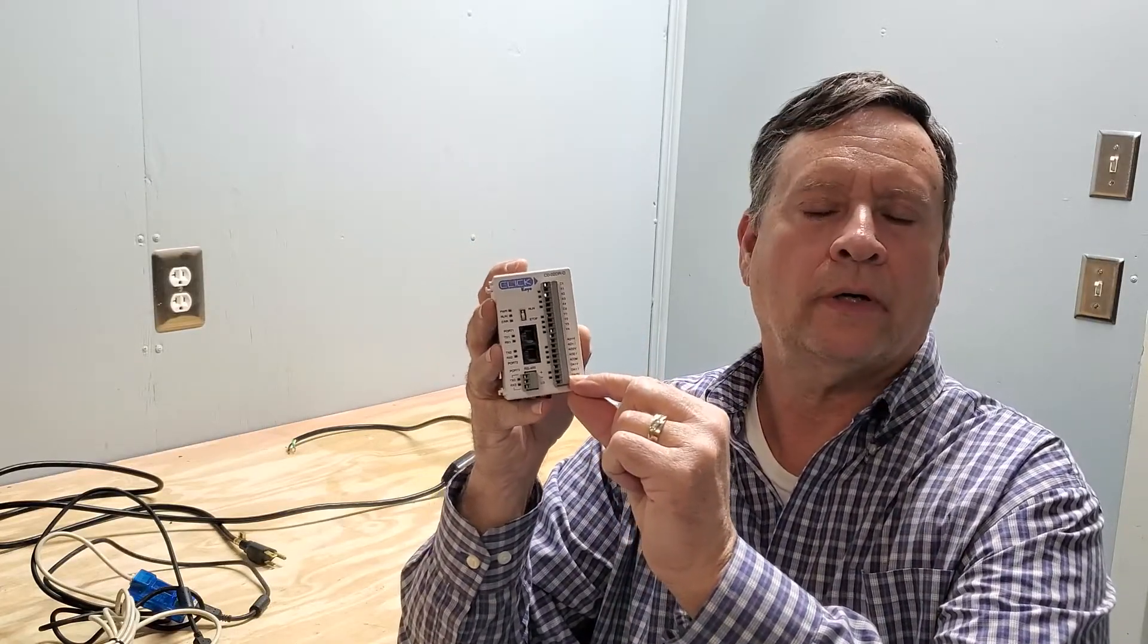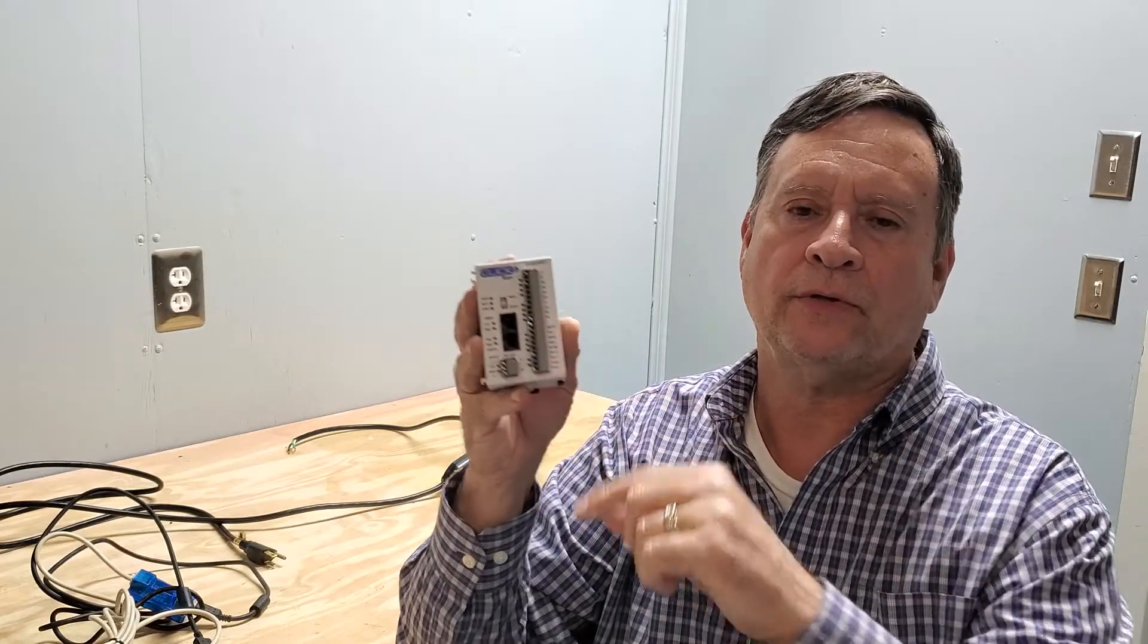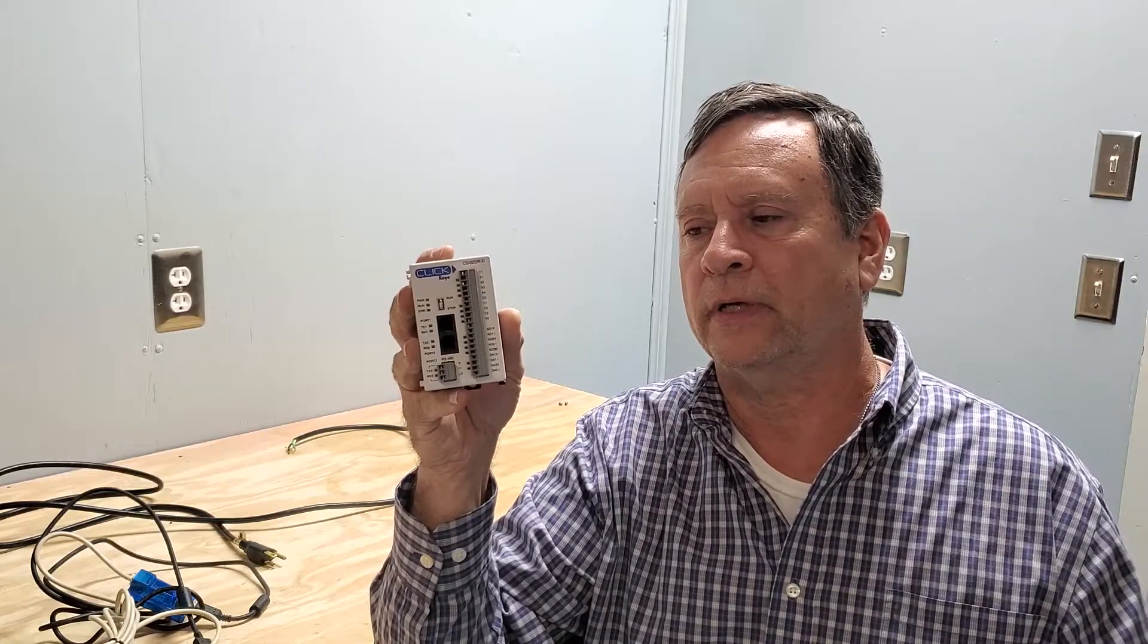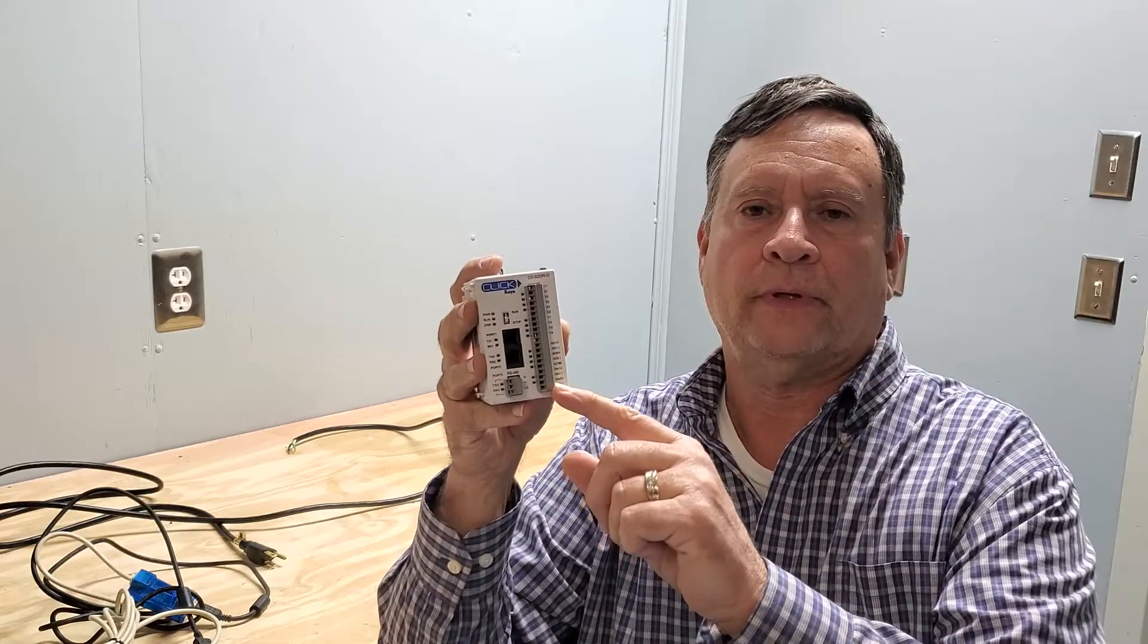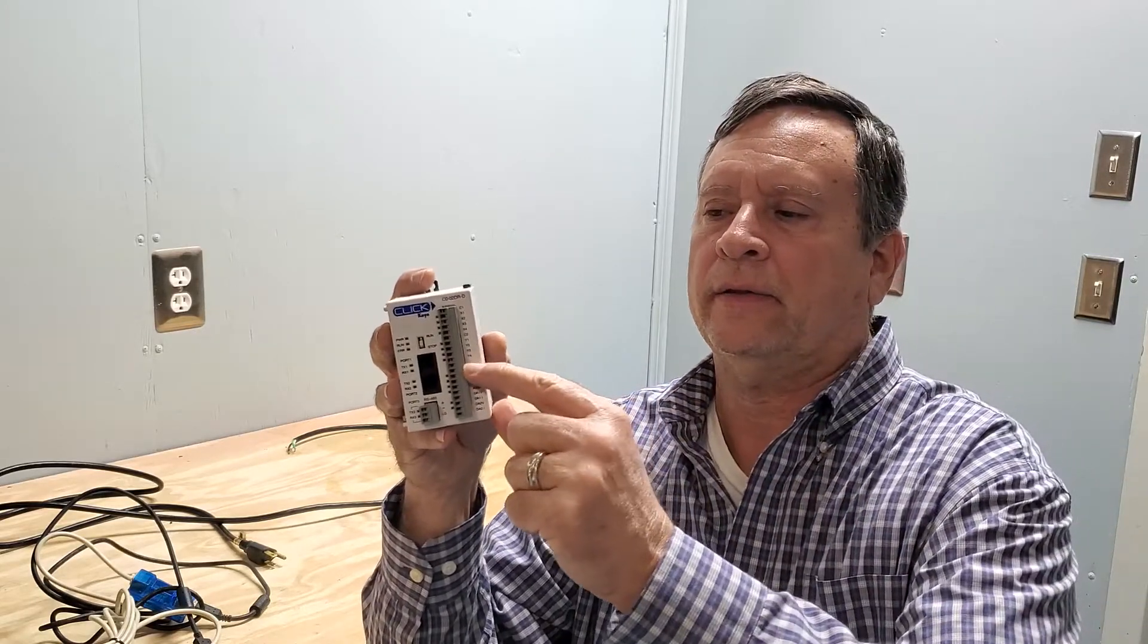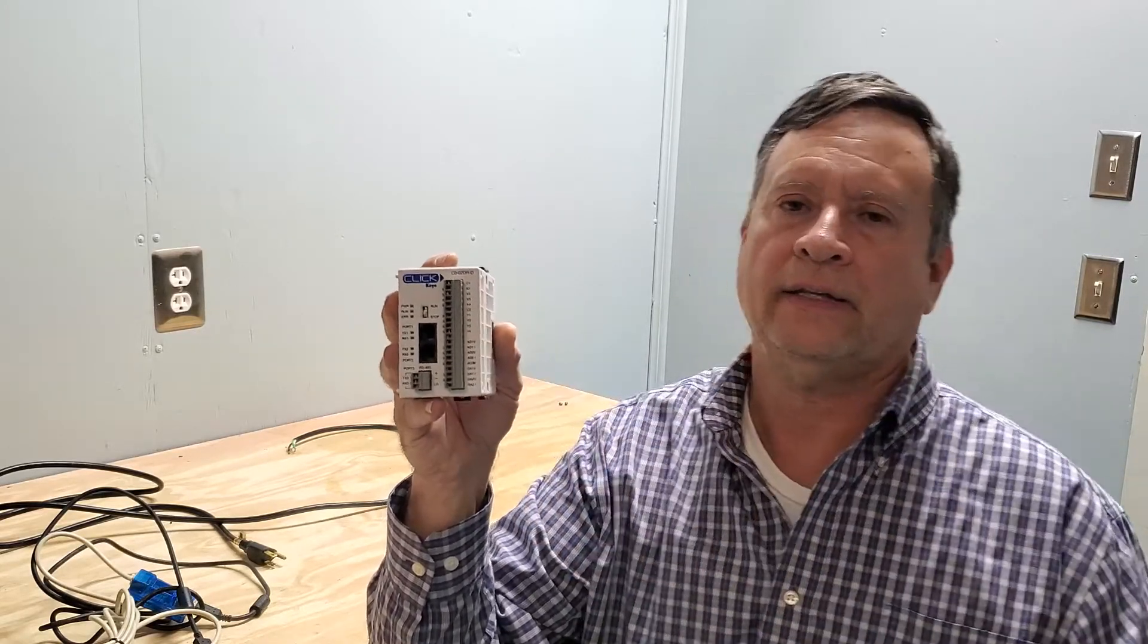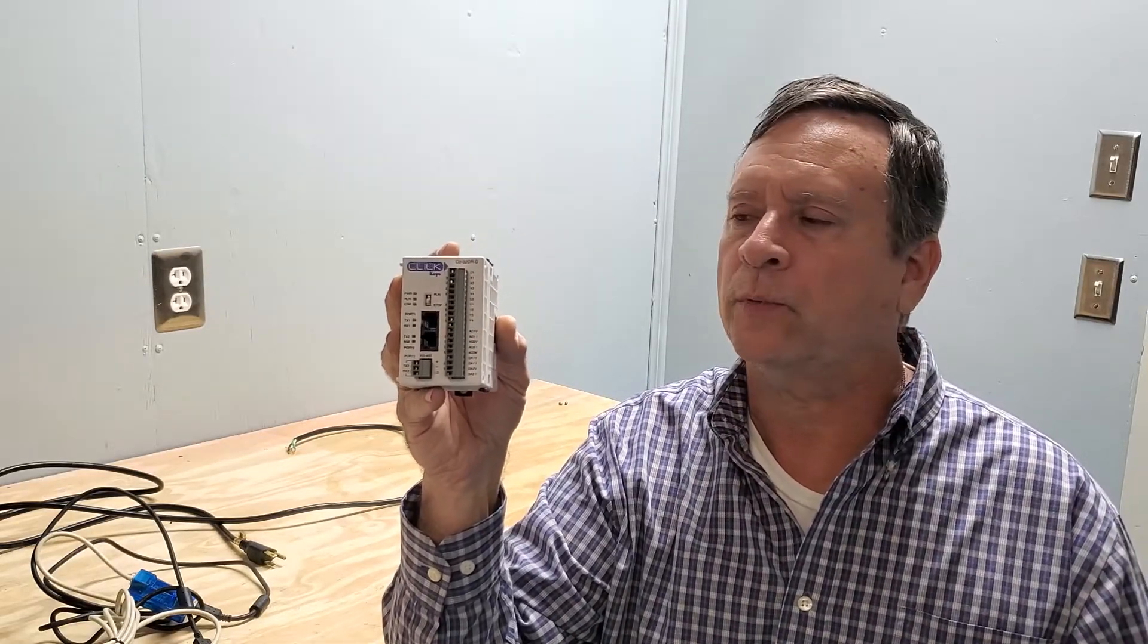And it has two analog outputs which can be used to maybe tell a motor control how fast you want it to run. You could use one of the outputs from there to tell it, do you want it to run at 47 percent speed. It'll have a zero to five or zero to ten volt signal coming back from it that can come back into this, tell it yes I am at speed. So for example, if it wasn't at speed from the display or from some other device, you can tell it to increase or decrease the speed to set the speed where you want.